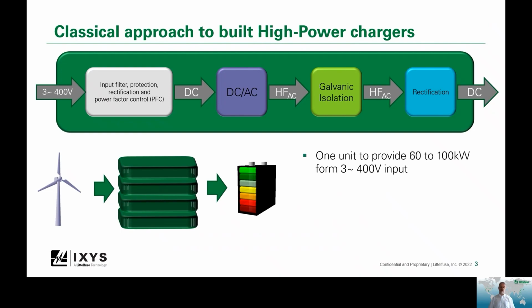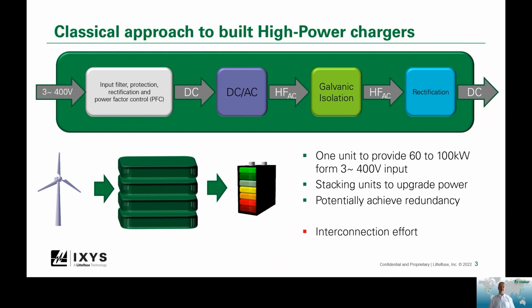In this case, each system takes three-phase 400 volts and converts it to DC at a power level anywhere between 60 and 100 kilowatts as of today. Those subunits are stacked, and that upgrades the power level. Potentially, it achieves redundancy as well in case of failure. Detrimental is the high number of interconnections that is needed, and additionally, there is one isolation entity in each of the modules, which may not be the best approach here.